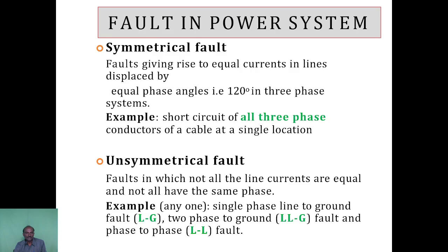Classifying the fault, we have two types, symmetrical and unsymmetrical. Faults giving rise to equal currents in lines displaced by equal phase angles. So in all the cases, we have equal currents. That is categorized as symmetrical fault. Example, short circuit of all three-phase conductors of a cable at a single location. That is categorized as three-phase faults. The other name for symmetrical fault is three-phase fault.